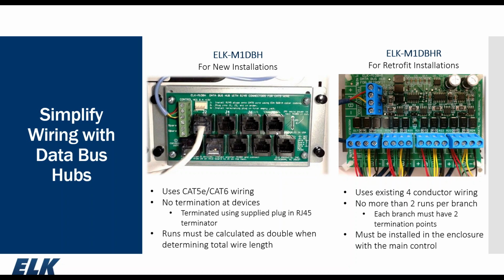You'll notice there are 9 ports on the DBH, and the DBH hub includes an RJ45 connector that has the resistor built into it. You can see it here in our picture in J3. As you add devices to the hub, you simply move that to the first available unused port. That way you don't have to worry about terminating in the field. There are 9 ports on this hub, but don't think you're limited to 9 bus devices. You're not. You can have 2 of these hubs in parallel. That would be your 2 home runs.